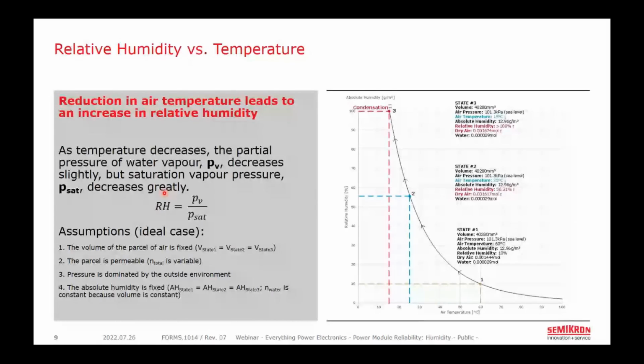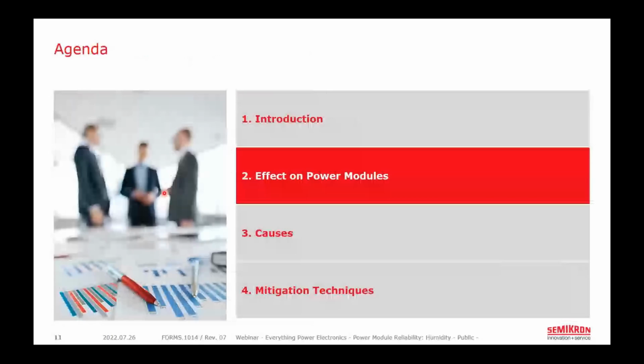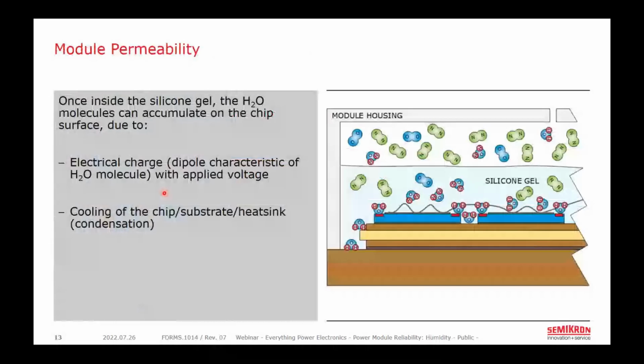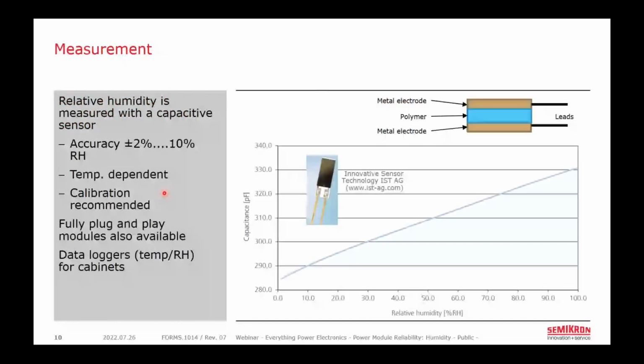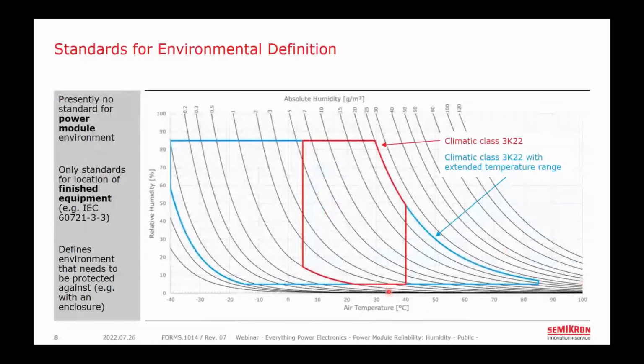Okay, makes sense. So for relative humidity, you talked about maximums and things. Is there any minimum required relative humidity for correct operation? Frankly, from a power module standpoint, I would say no. But unfortunately, in the climatograms that are defined here, you can see the minimum happens to be 5%. That's just the way the IEC has decided to define these environments.